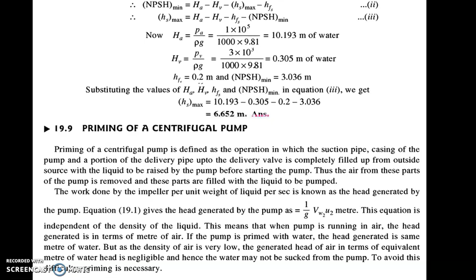But as the density of air is very low, the head generated by air, equivalent to meter of water, is very less or negligible. Hence the water will not be lifted or delivered. Hence water may not be sucked from the pump. To avoid this difficulty, priming is necessary. So priming, you remember, is necessary for removing the air inside the pump. Otherwise water will not be sucked by the pump.